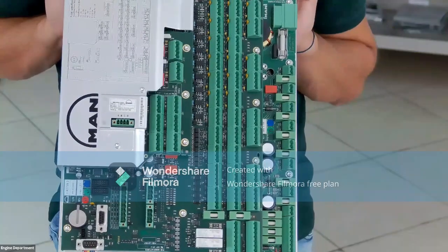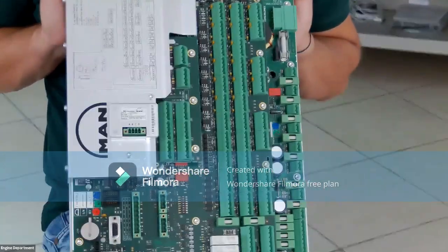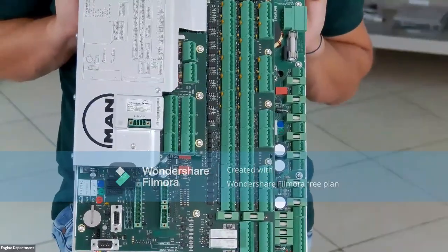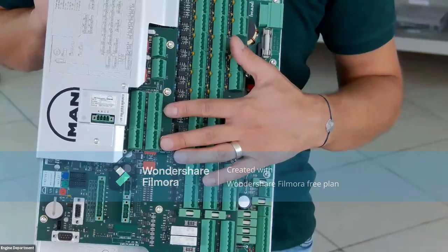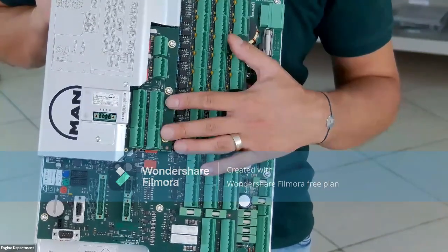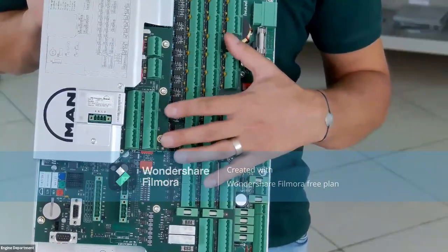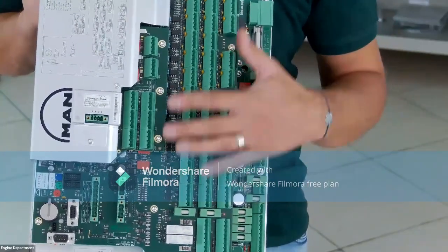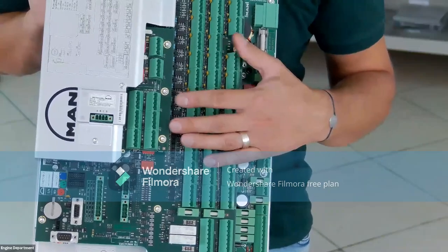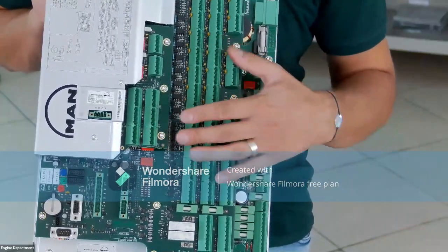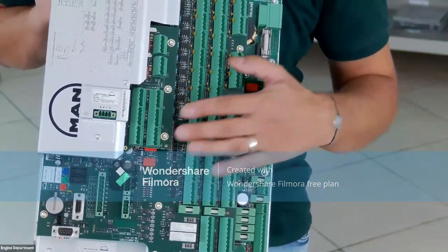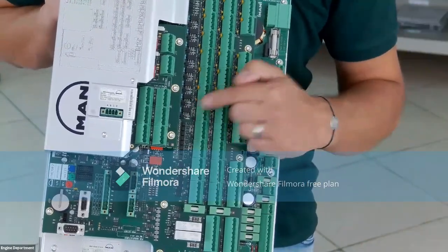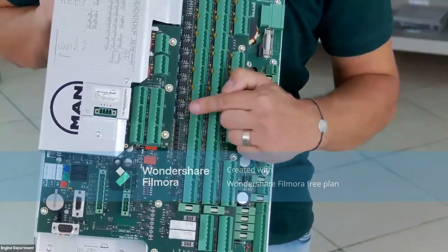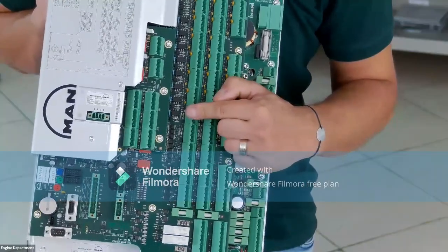Yes, we are checking the switches, but because we didn't know the source of the provenience of this MPC, I want to install a CCU on the CCU3, but this is old one. If this MPC was used a CCU3 on other vessel, when I connect the ID key it will tell to this MPC, you must be CCU3. And this MPC, it will give the answer, I am CCU3. And it will not be any conflict.